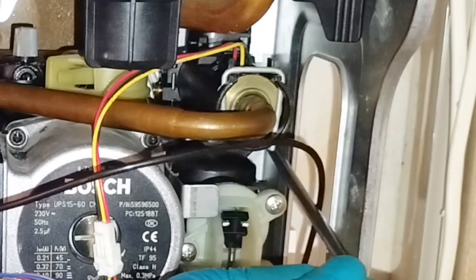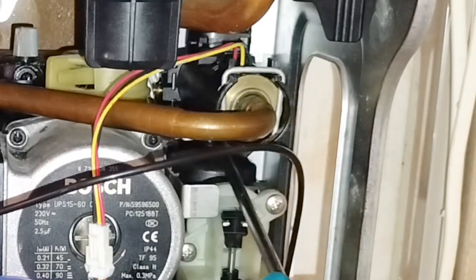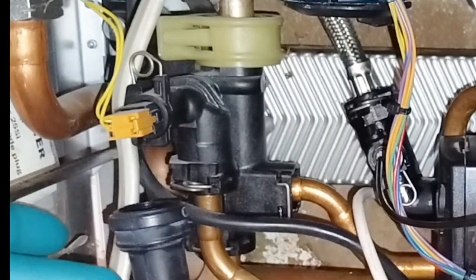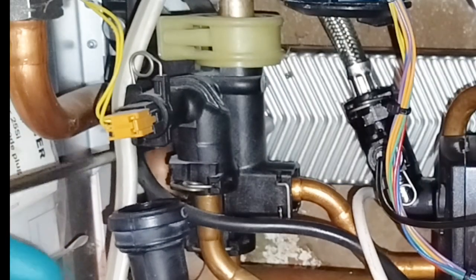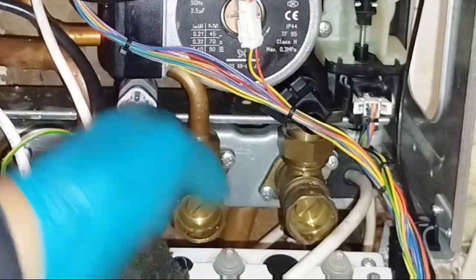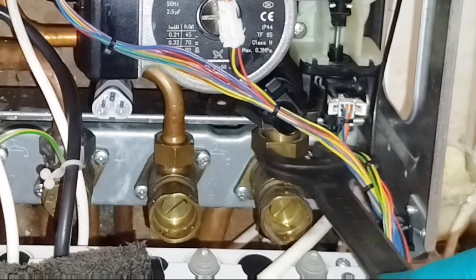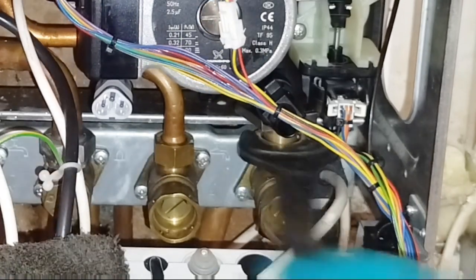Now to finally tighten the retaining screw and make sure all the screws are tightened on the plate heat exchanger, on the manifold itself, especially the one which we've replaced. Now to tighten up the nuts on the cold water supply and then the heating return pipe. Don't go crazy when tightening.